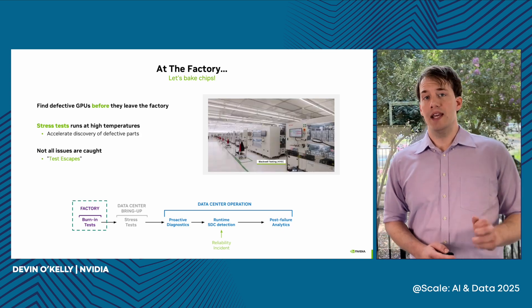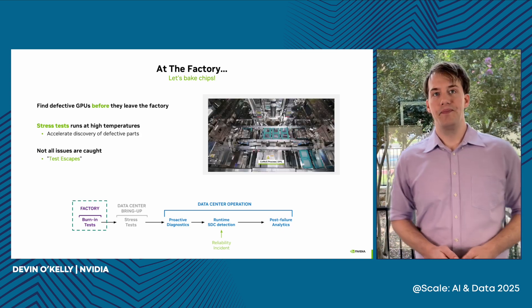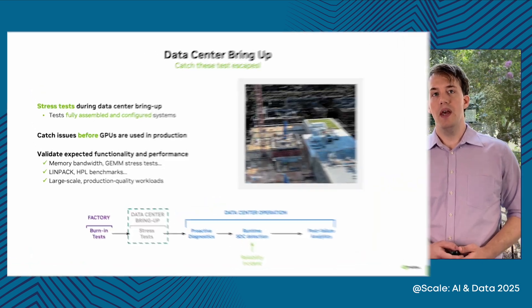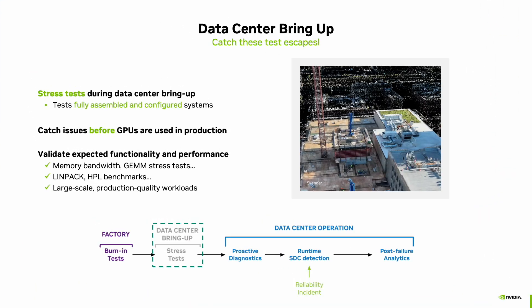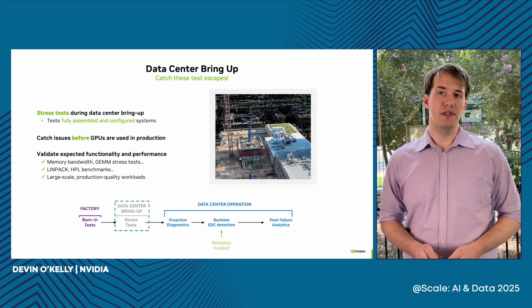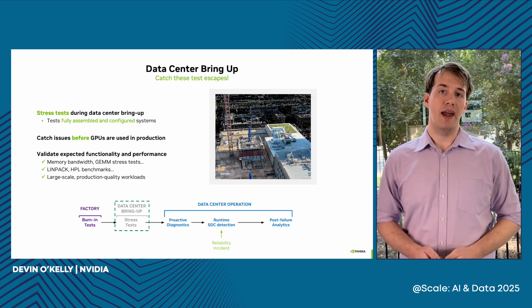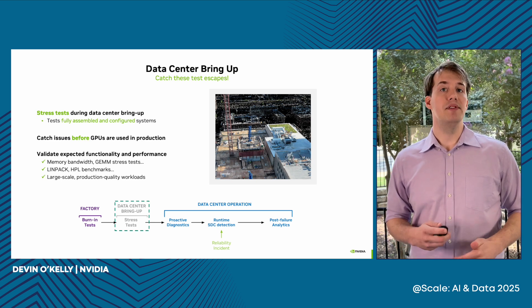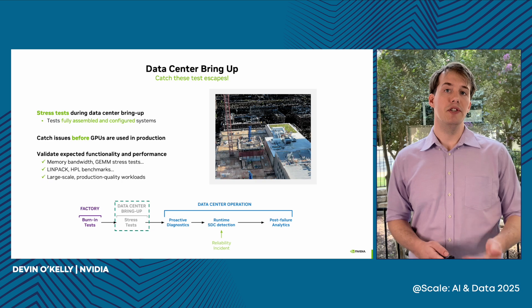We address these so-called test escapes by validating GPUs in the field. Our next line of defense takes place in the data center during the initial bring-up and validation phase. We run another batch of screening tests on fully configured and connected clusters, ensuring that the GPUs can sustain the intensive training workloads we expect in production. This includes benchmarks to verify the system is operating at full performance, and burn-in tests to ensure that performance remains stable over hours and days of continuous use.